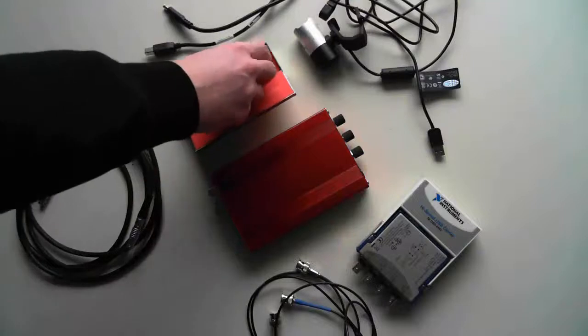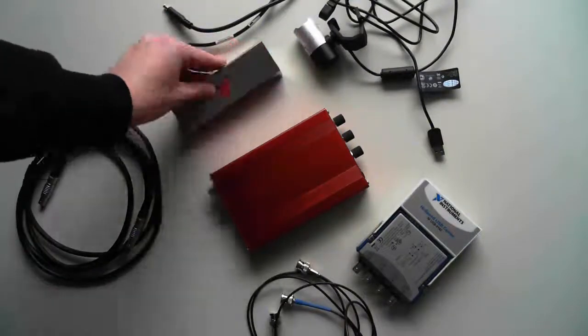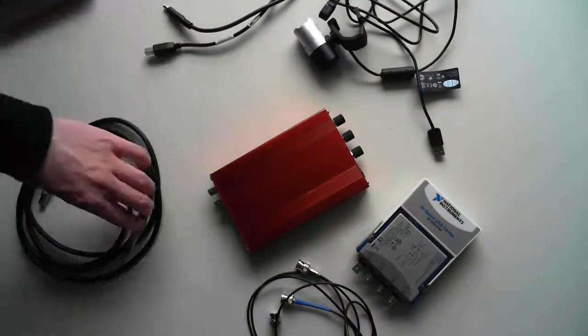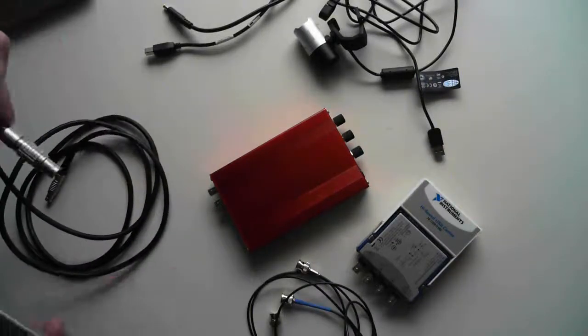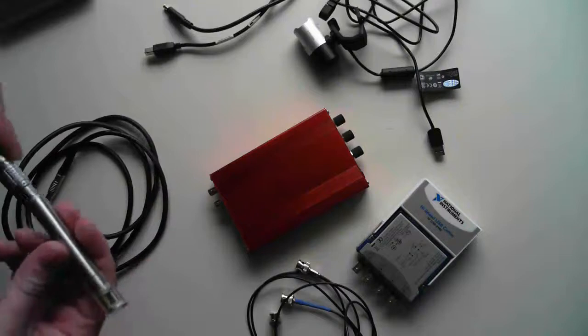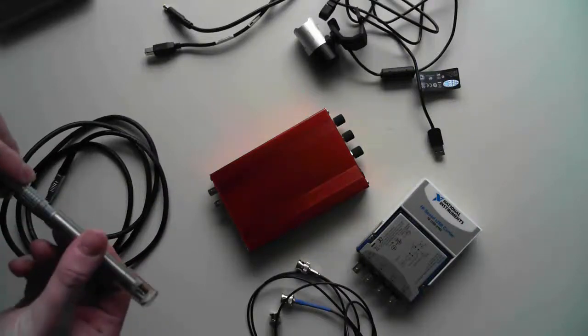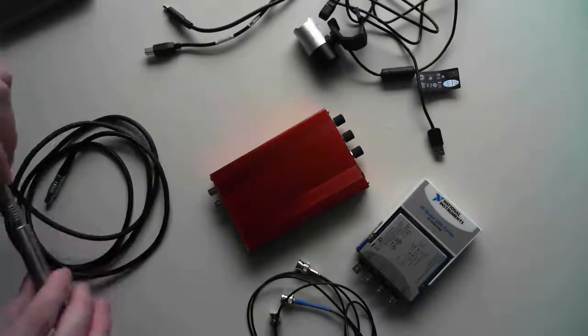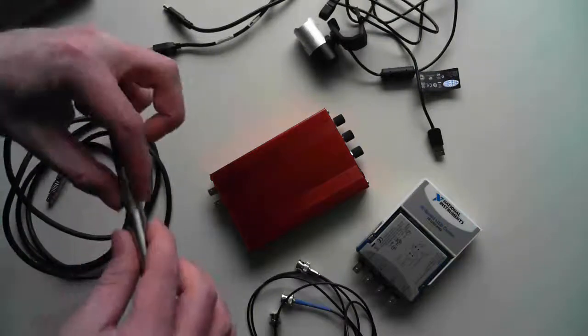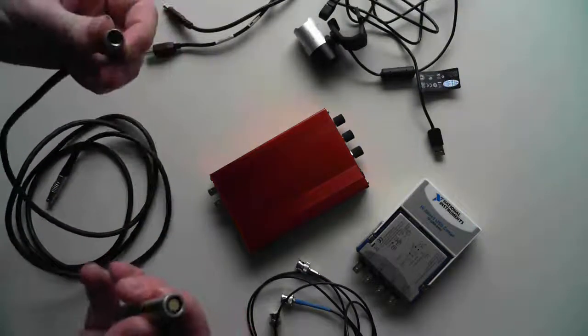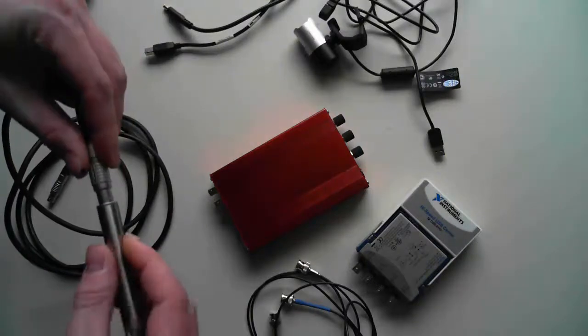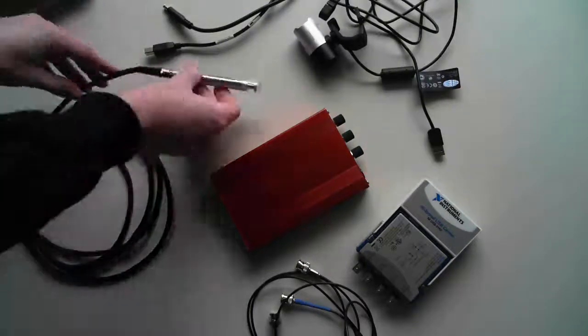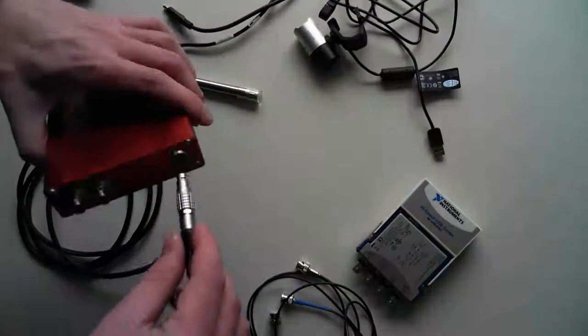First we connect the Intensity Probe with the Amplifier. To do this we just connect these high quality Lemo jacks with the Intensity Probe. There is just one way to push it in, so nothing can go wrong. To disconnect, we just have to pull, and the same on the amplifier side.